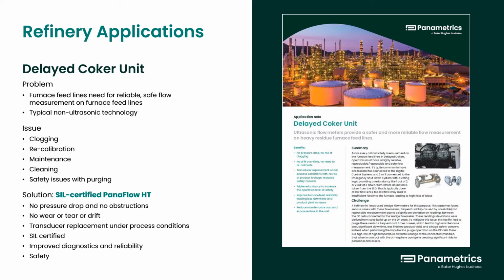Beyond clogging, recalibration, maintenance, and cleaning were common due to inconsistent measurements between the multiple flow measurements due to the clogging impulse lines and blocked membranes. Therefore, technicians were continually required for servicing these meters, which led to lack of trust in the measurements. Along with the maintenance, there was always concern about safety, with purging existing meters and exposure to technicians in these situations. The solution to these applications is our Panaflow HT ultrasonic flow meter.